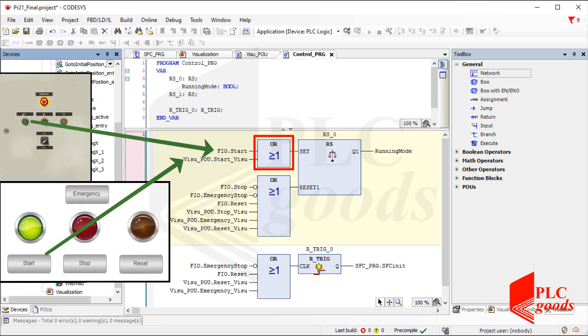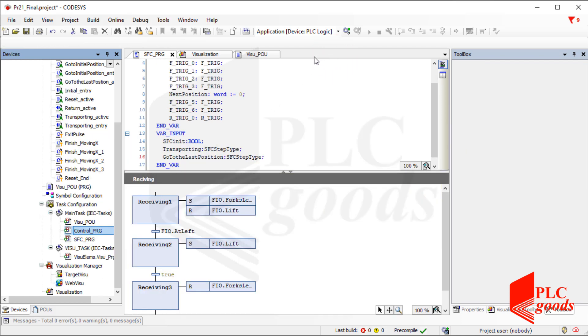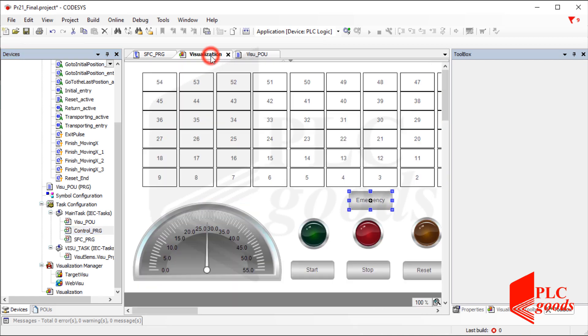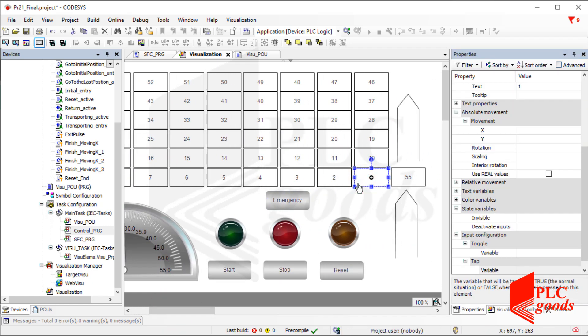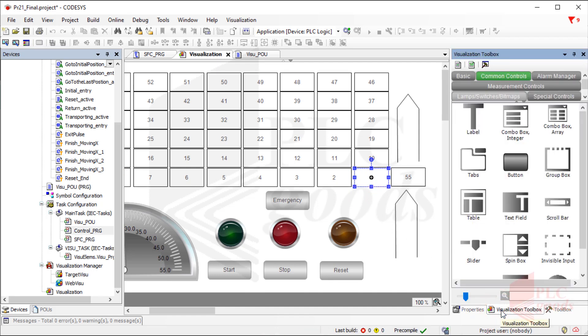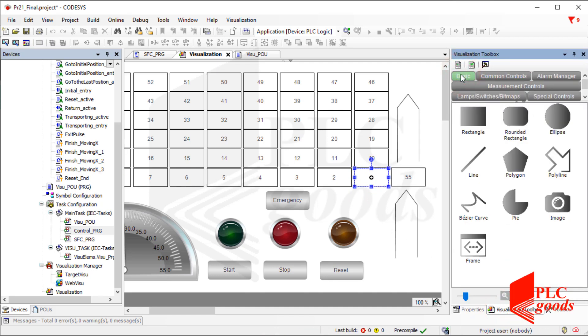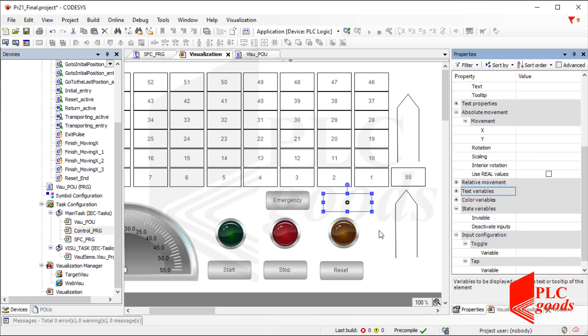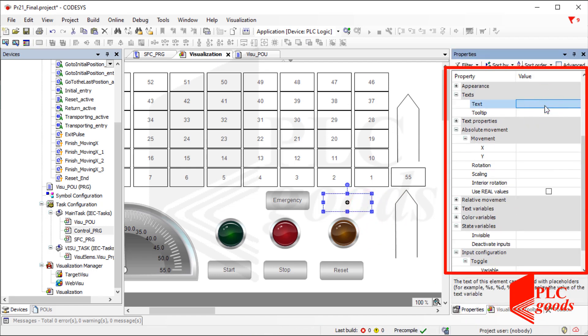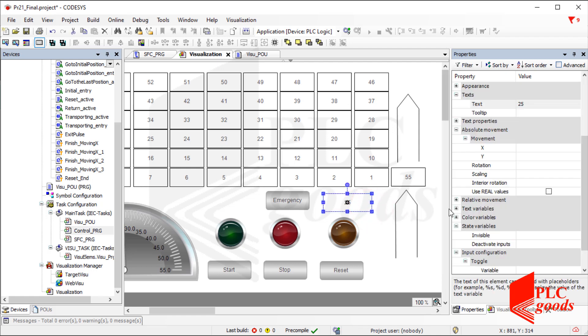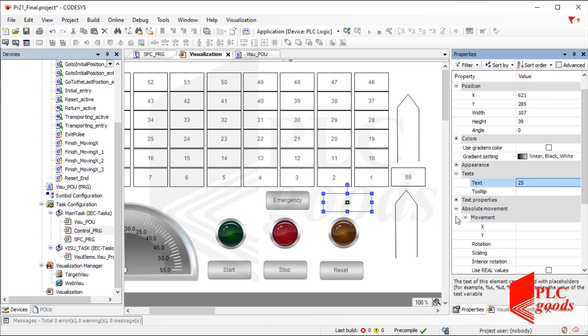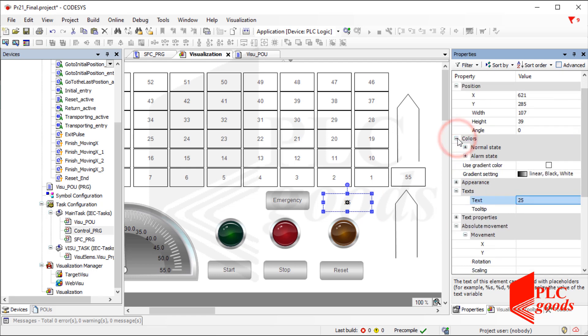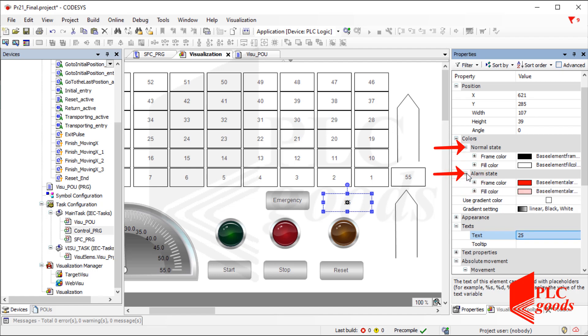For example, using this OR logic, the start push button and also the start button on the design screen can be used to enable the running mode variable. As you see, I've used 55 simple rectangles. A simple rectangle can be added from the basic objects. As you see, each object has some properties. For the inserted rectangular, I can define a static text or number. Also, each rectangular has a color variable. It determines which colors should be used. It selects one of these two modes, the normal or alarm state.